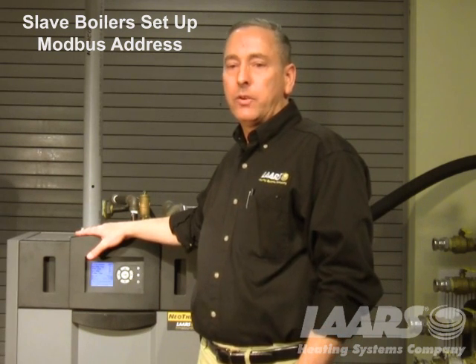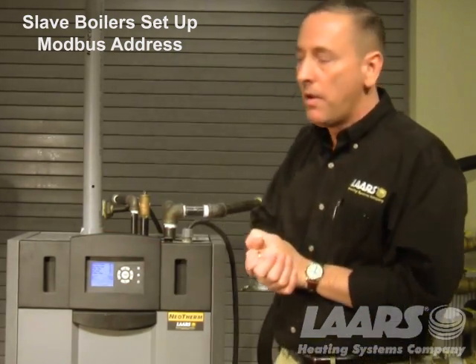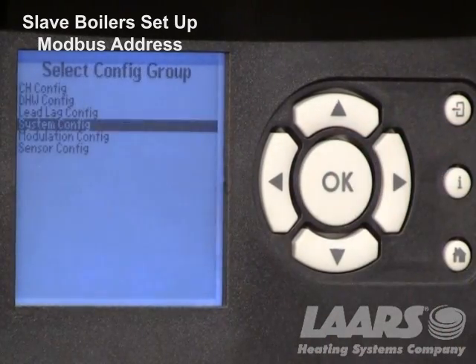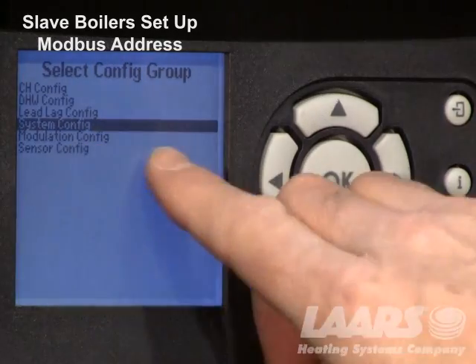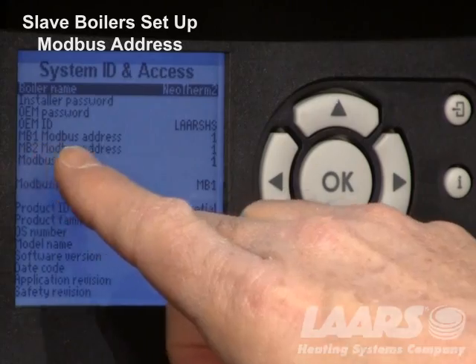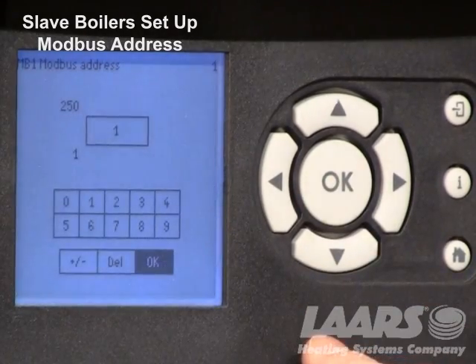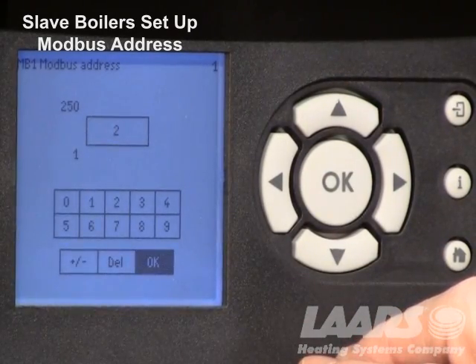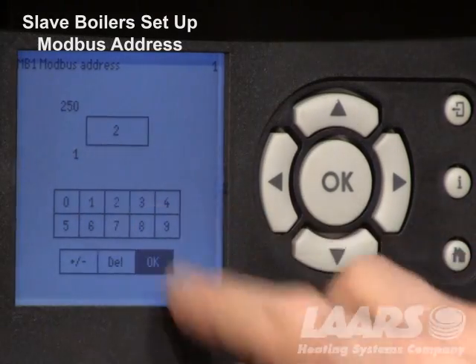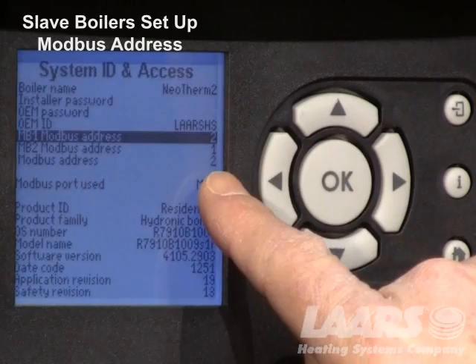Now that the master control is programmed, we go in and program the lag boilers by changing the Modbus addresses for each slave control. From the home screen, press the information button, choose advanced settings, go down and choose system configuration, click okay. System ID and access — press okay. We need to change the Modbus addresses for each one. Highlight the MB1 address, click okay, and choose 2 for boiler 2. If working on boiler 3, choose 3 or 4, et cetera. Click okay and you'll see the MB1 address change to 2. You'll also see the Modbus address at the bottom has changed to 2.